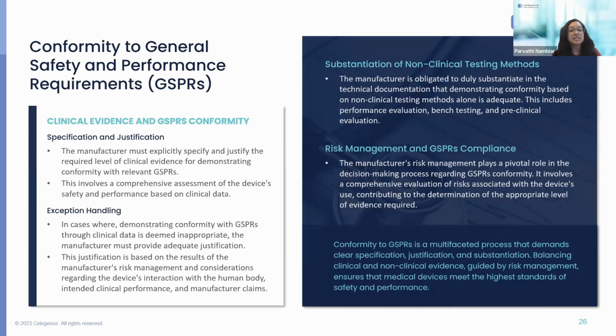Additionally, to show that the device performs as intended, we need to present data related to the non-clinical testing that has been carried out, such as design verification and validation tests, or shelf life stability tests. Data from the literature also needs to be presented to demonstrate that the device, when used in patients, performs as intended. The other thing to check is to demonstrate that the device does not have any side effects, and that anything that has come up in the adverse event databases are known risks. There have been no new or unknown risks, or in case there have been any new risks, they need to be mapped to the technical file accordingly.